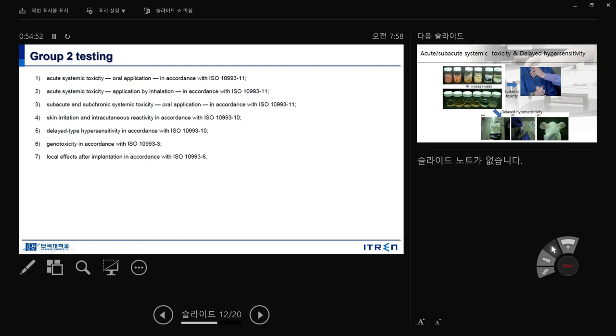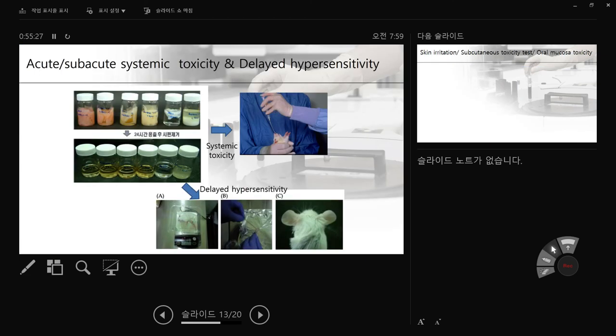Group 2 animal safety tests include: acute systemic toxicity via oral or inhalation route, sub-acute and sub-chronic systemic toxicity, skin irritation and sensitization, intra-cutaneous reactivity, delayed-type hypersensitivity, genotoxicity, and local effects after implantation. For acute and sub-acute systemic toxicity: if you have nanoparticles, you can inject IV or give orally. For hard implant materials, you extract from the material using oil, PBS, or distilled water after 24-hour extraction, then feed the extract to mice or rats daily for one week, one month, or two months, and check organ histology.